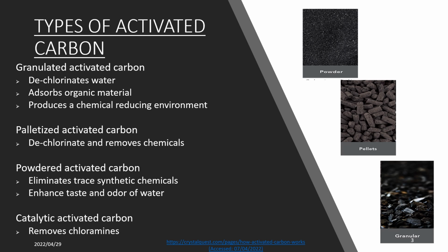and removes the chemicals. Then we have the powdered activated carbon, which is good for eliminating trace synthetic chemicals and can play a role in enhancing the taste and the odor of the water. Lastly, we have the catalytic activated carbon, which is used for removing chloramines from the water.